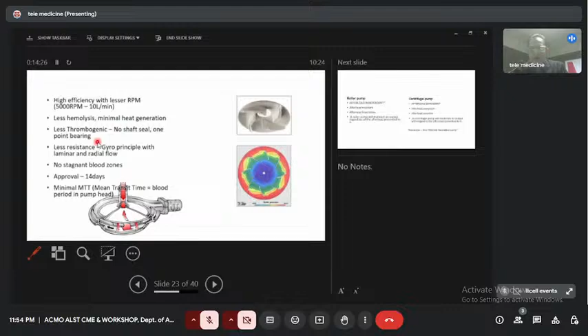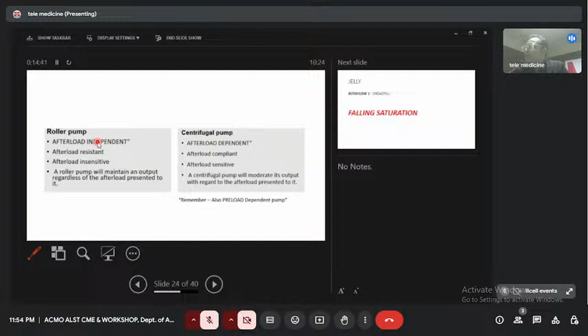So this is the basic funda. That's why we have approval of 14 days, and there is a minimum transit time, mean transit time, sorry. The blood period in the pump head is quite decreased with this centrifugal pump. That's why this pump is used for long days, even months. So this is the difference I told you already. It has to be afterload dependent and preload dependent also. So it causes minimum injury. Okay, you can afford some injuries at the cost of life.